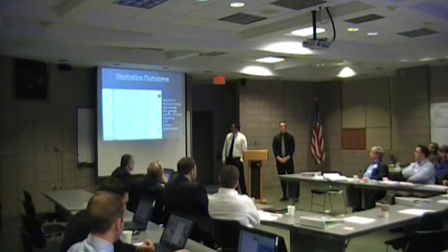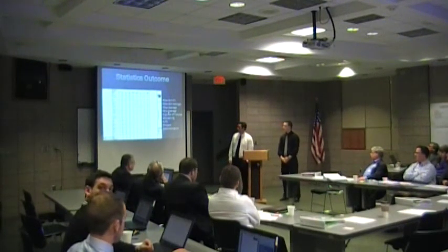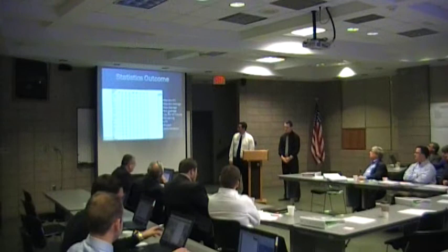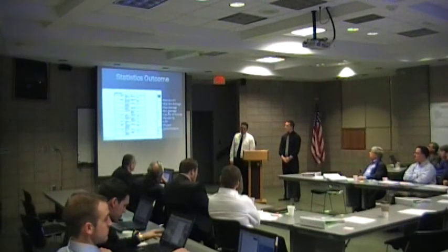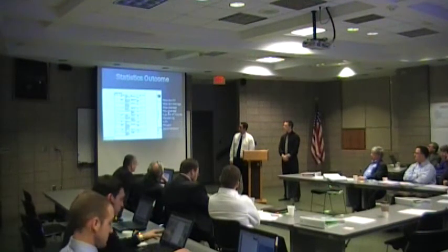The statistics that it provides, it gives you the maximum, minimum foot candles, the maximum average. It'll lay out the fixtures for you. It can render them for you. It automatically creates your light fixture schedule and gives you other project documentation that you can follow that's very useful in your projects.